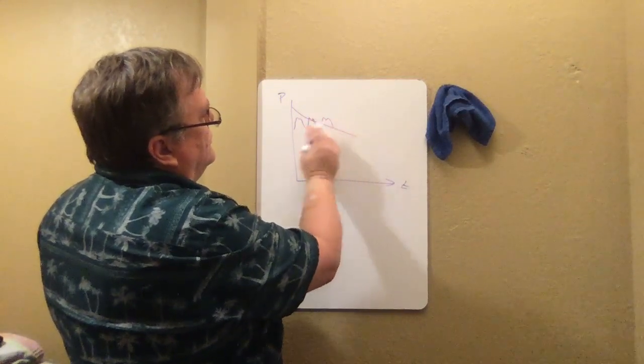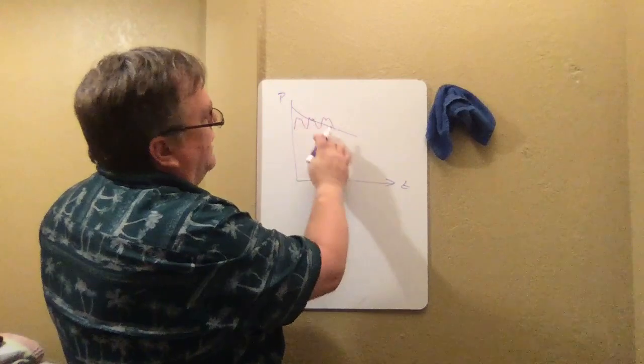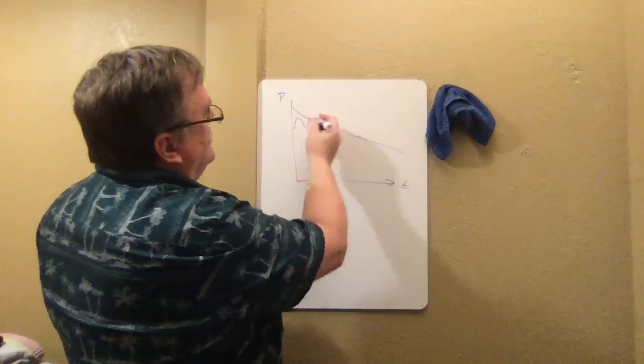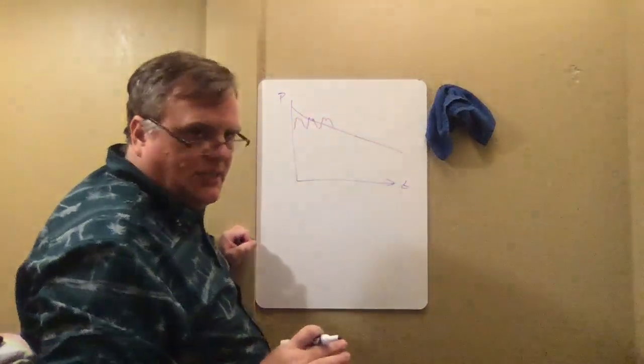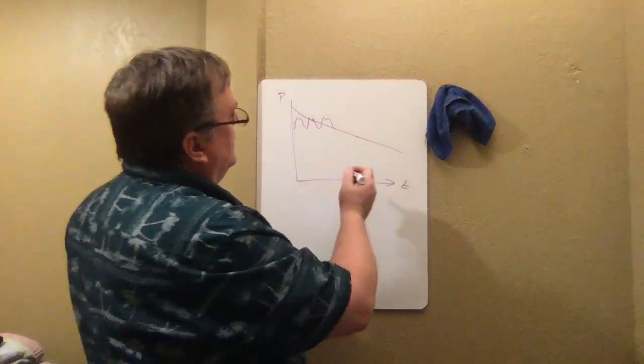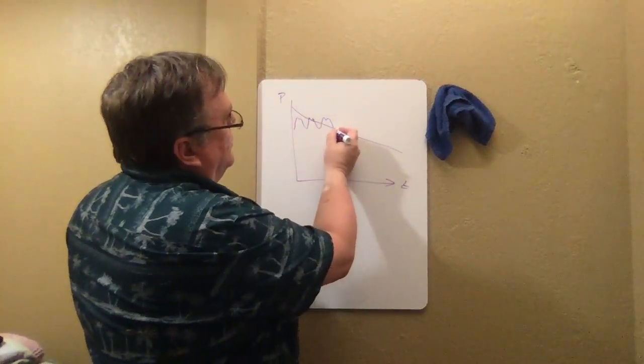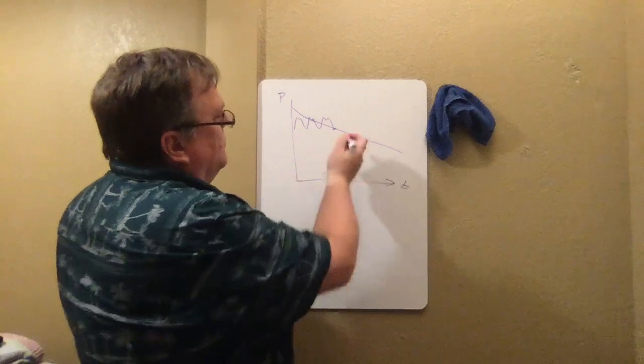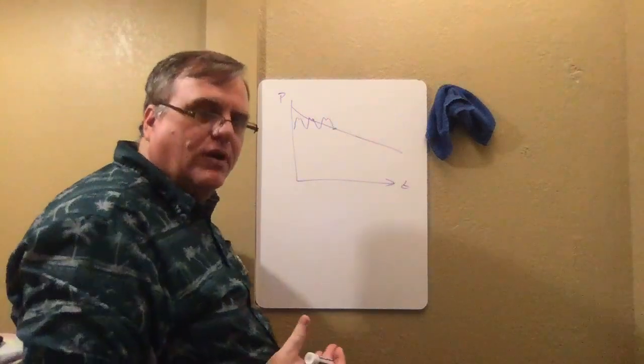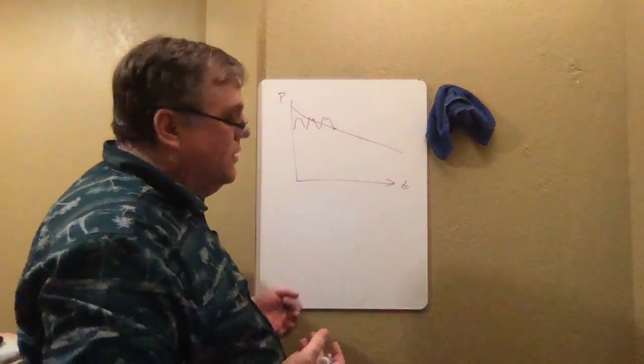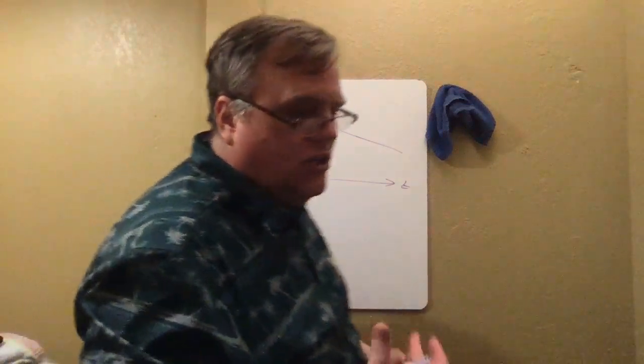Now, the reality is this wave is much, much faster than this decay is, so it sounds pretty much continuous once it's opened up. And at a certain point, it'll hit the bottom, and below that, it's not enough to cause any compression, so the noise goes away. So if you're doing it by the auscultatory technique, right?